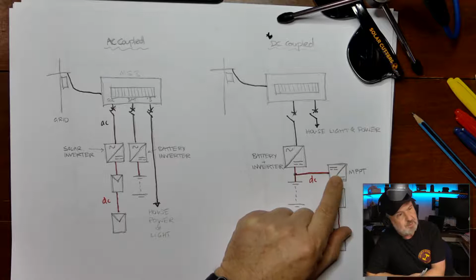So that's DC coupling, but note the difference, only one inverter. You don't have utility approvals for the DC coupled side of the system. You don't have to get an approval to put in an MPPT. And what that means in practice is this part of the system is up to you, up to the customer, what they want to install, how much. They're not limited by any rules around maximum inverter capacity.